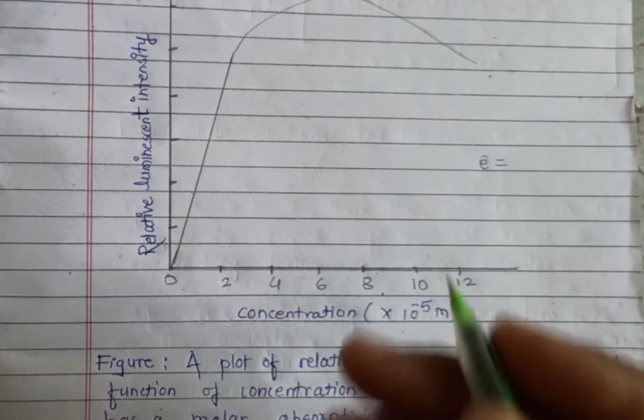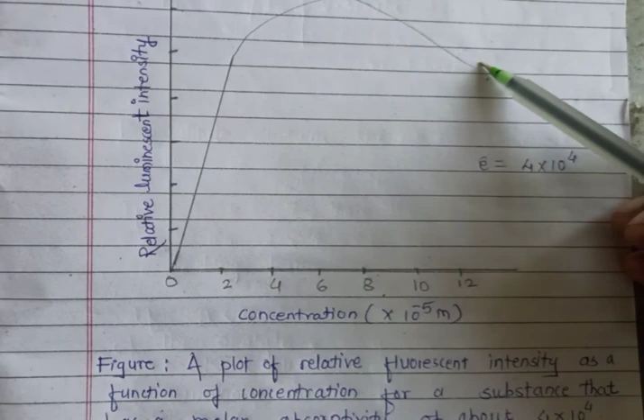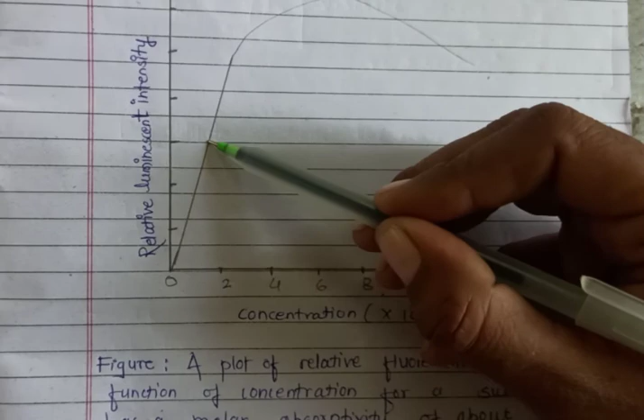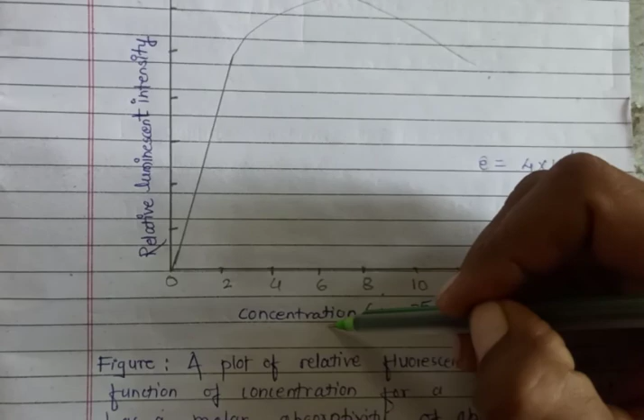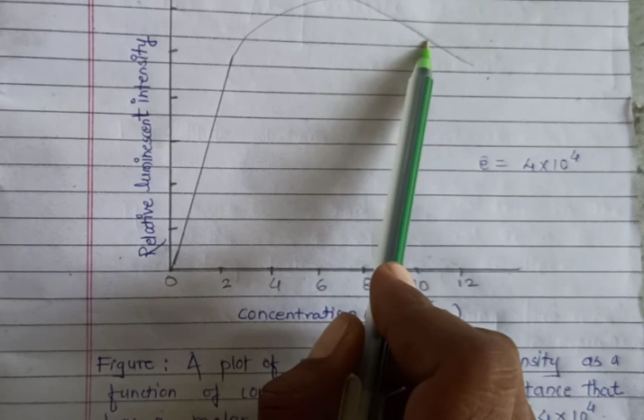Most instruments are designed to measure luminescent intensity in the center of the cell, where the decrease in intensity can be significant at high analyte concentrations. A plot of luminescent intensity as a function of analyte concentration often goes through a maximum and actually decreases at higher concentration. When initially the concentration is less, there is a positive relationship between fluorescence intensity and the concentration. But when the concentration exceeds this, the maximum is observed, and at very high concentration there is a deviation, and the straight line nature is deviated, so the assay solution can be diluted and the luminescence is remeasured.